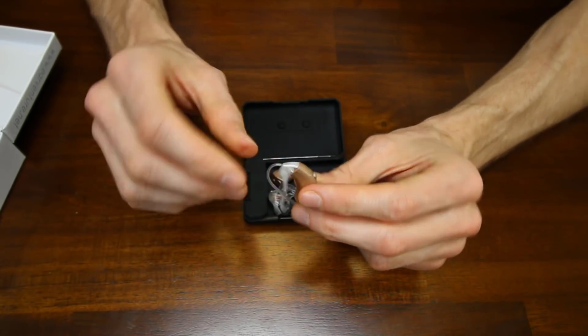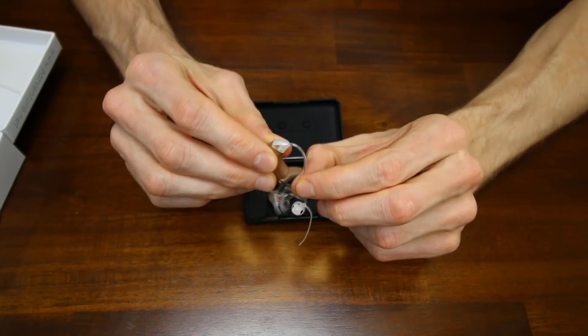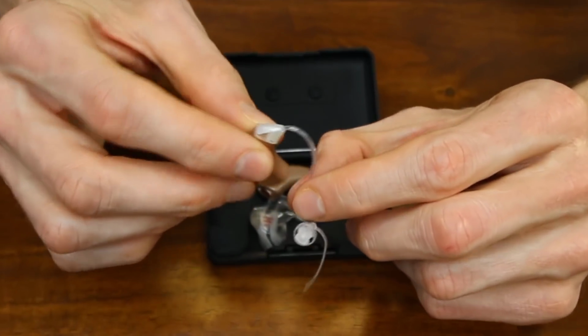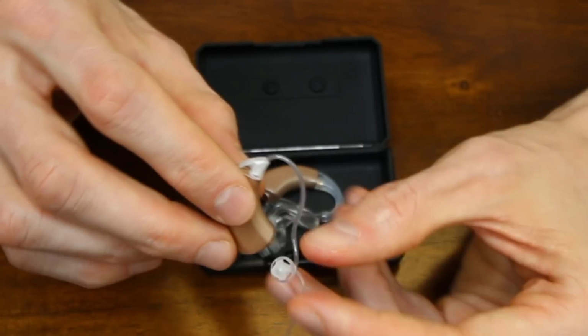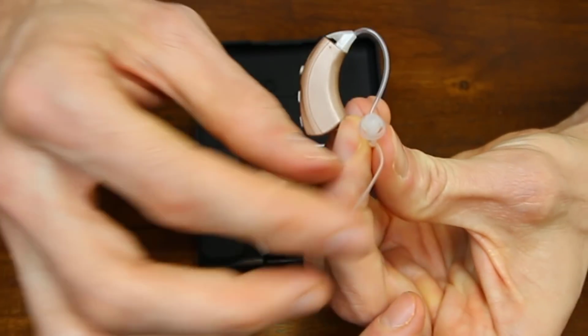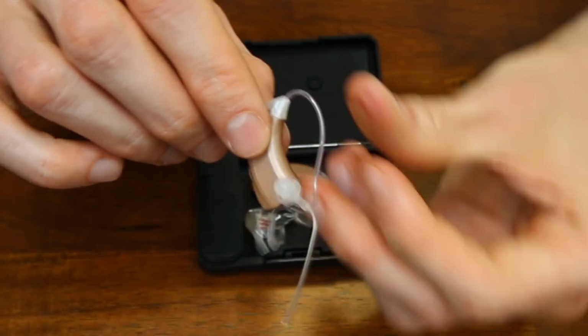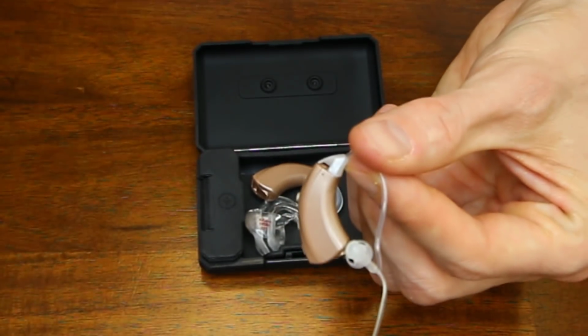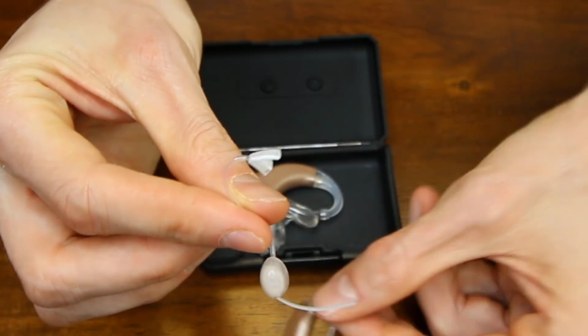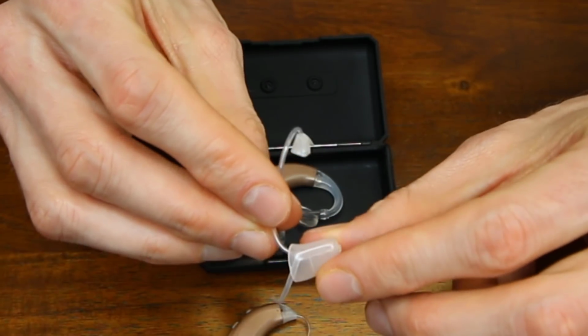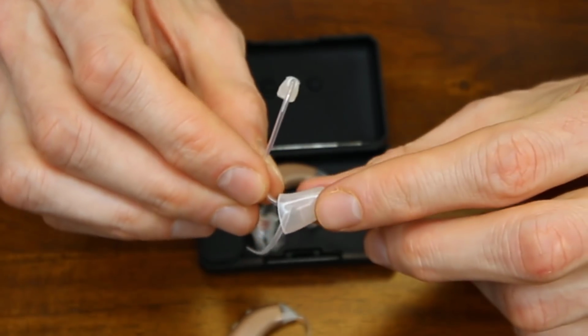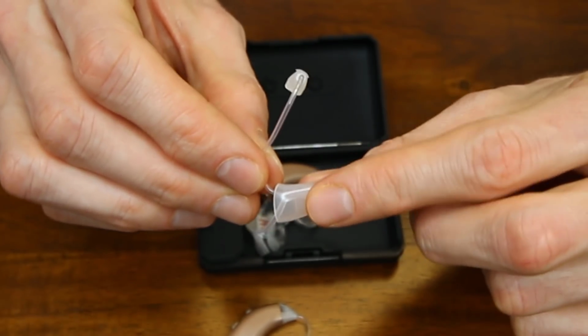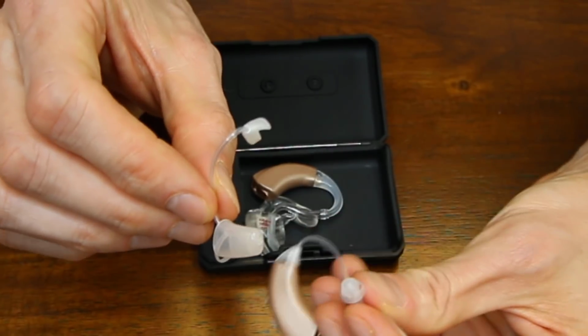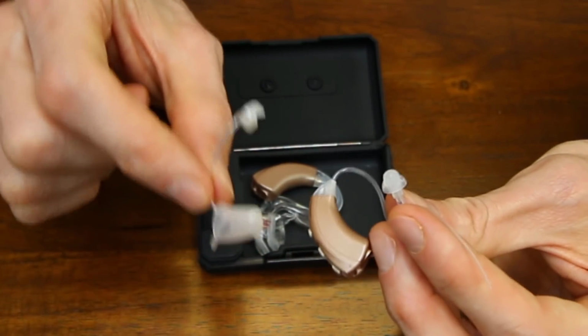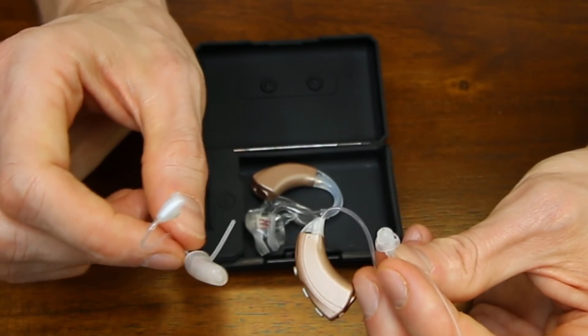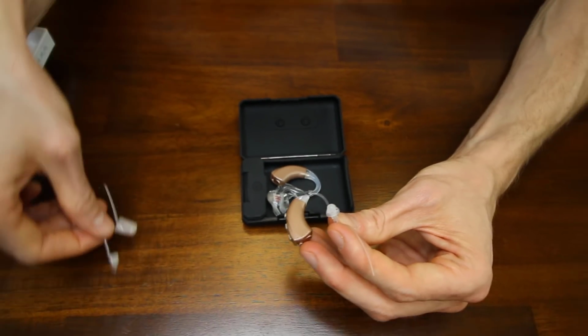What we have coupled onto it right now is a slim tube. So this is your most invisible option that you have. This will go down into your ear and it has a dome on it and a little retention filament to keep that inside of your ear. But you also could use any different type of attachment at the tip here to make sure you get a better customized fit. You can even have a custom ear mold done to have a custom tip put on the end of this slim tube. It's really good if you want to control the amount of sound that goes in to your ear from the hearing aid to make it more of a customizable device.